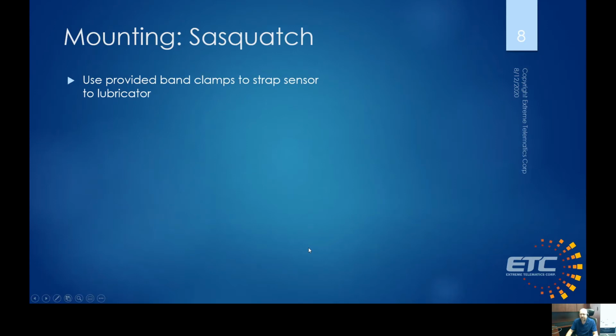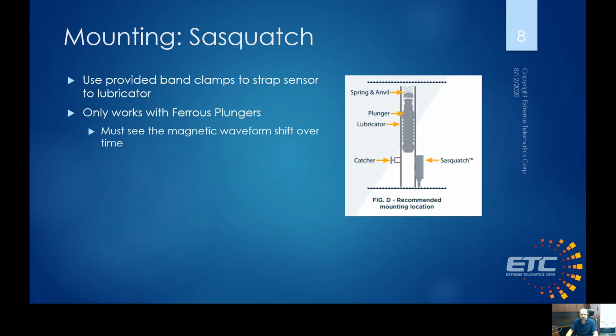Now with the Sasquatch, it's the same kind of mounting. We actually provide two band clamps. It has two sets of legs, securely to the lubricator again. And the Sasquatch only works with ferrous plungers. Because we require multiple data points, we need to see the plunger travel by the Sasquatch. So we need to have multiple waveforms so that we can correlate them. And so the plunger must travel all the way by the sensor.